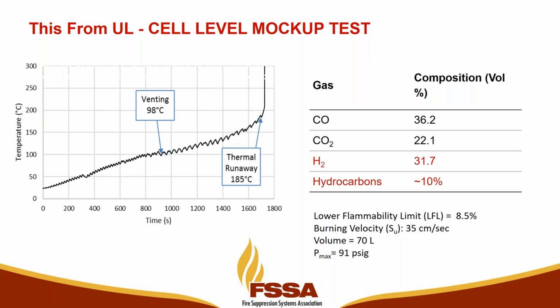The cell testing isn't that bad. So if they can show limited propagation beyond a module, then they really shouldn't need to do further testing beyond that. But it's not pass-fail - it's 'here's what happens.' There's no end result that says yes you're good, no you're not. Thermal runaway - you're going to get thermal runaway in a battery. It's going to happen to some extent. The question is does it ignite, does it propagate?